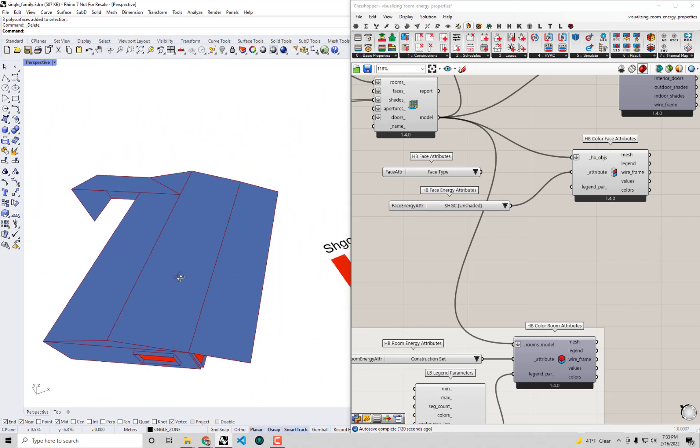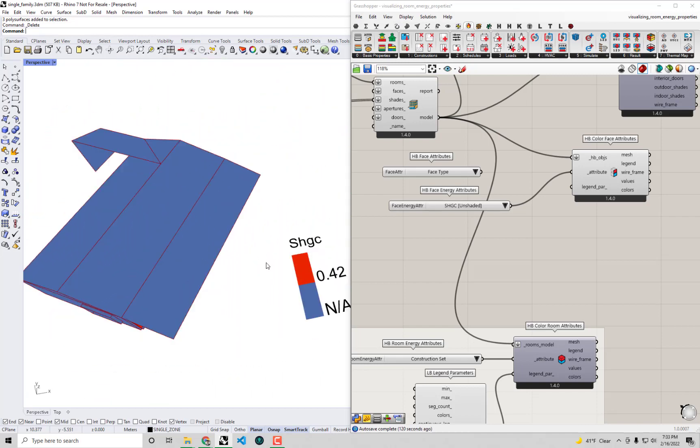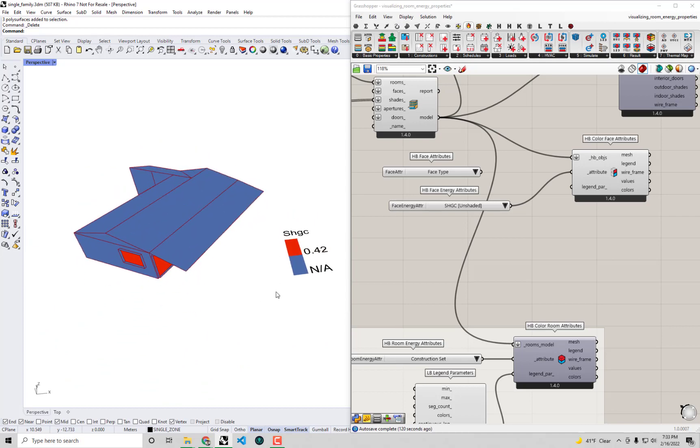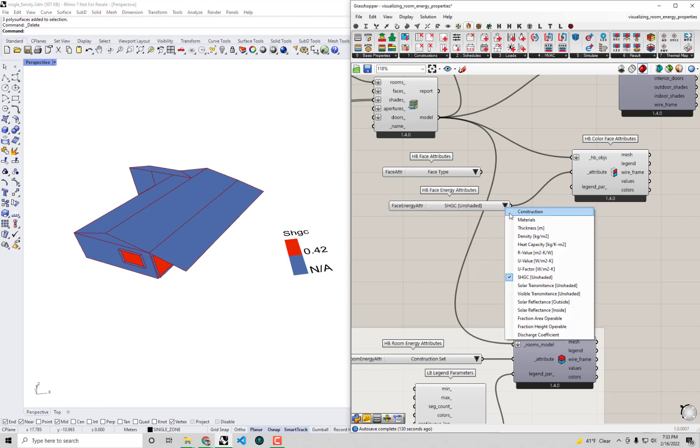This is definitely not a solar heat gain coefficient that was made for the climate of Southern California. Maybe the R values could be acceptable for this case but I can tell right off the bat that this is a set of constructions that are not made for this climate here.